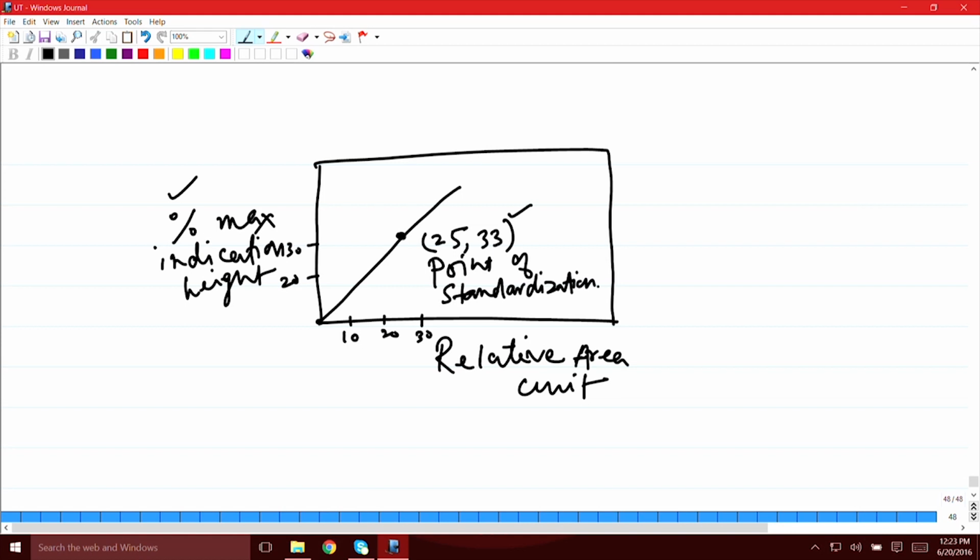Okay. And then you see the rest of the points, where they are falling, whether they are falling on this curve or if you note any deviation, you simply have to note that deviation for a particular hole size, and when you do the test, this is the correction that you need to provide, okay, for that particular size.